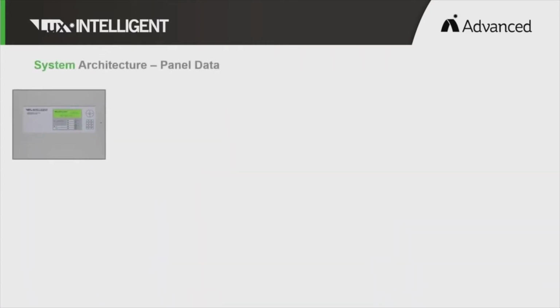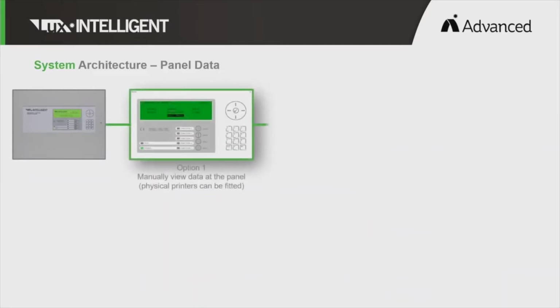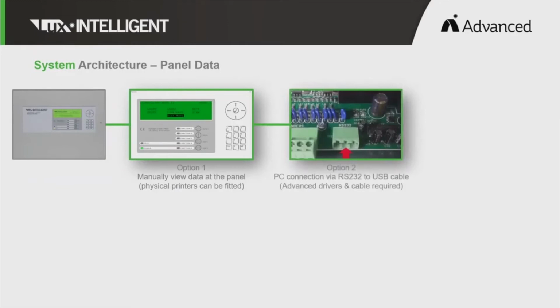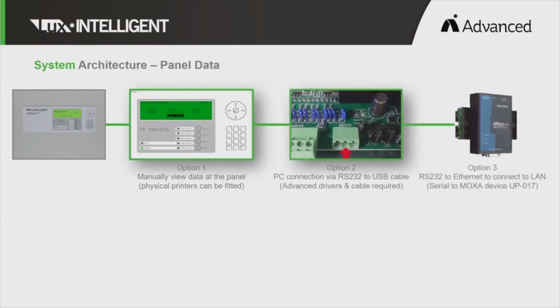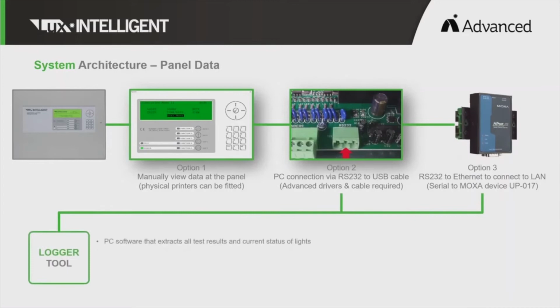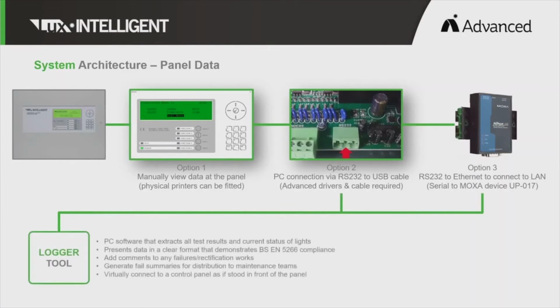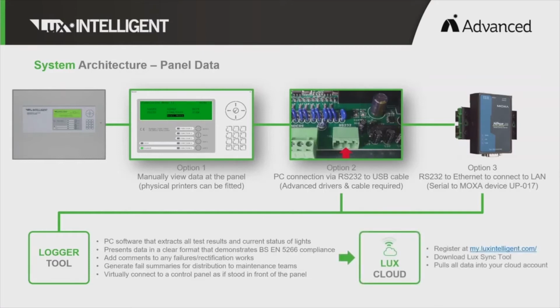There are numerous ways to view the testing and maintenance data from the panel. Firstly, there's manually at the screen, by connecting directly via cable, or via serial to Ethernet modem. The last 2 options give you access to the logger tool, a piece of software that can download all proof of compliance tests, as well as failure data and present it in various formats. It also allows users to add their own comments with regards to failures and rectification works and distribute it to colleagues or maintenance teams. A step above this is to move that data from the logger tool into the Lux Cloud.